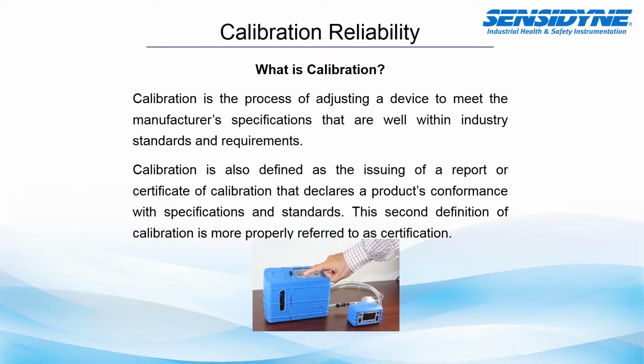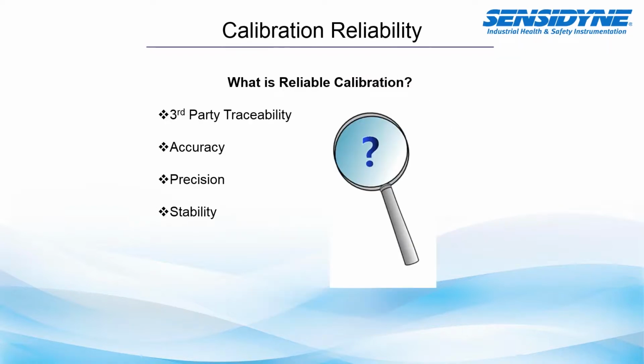Now, calibration is also defined as the issuing of a report or certificate of calibration that declares a product's conformance with specifications and standards. It's this second definition of calibration which is more properly referred to as certification. And this is really the certificate that comes with your calibrator, which makes it traceable to a higher level. So in talking about reliable calibration, we'll go over third-party traceability, we'll go over accuracy, precision, and the stability of both the calibrator and the source, the pump, that it may be calibrating.